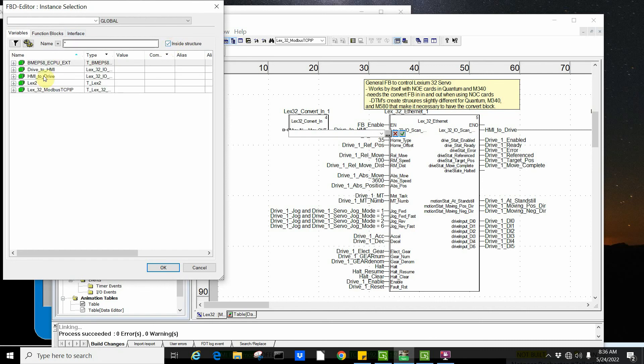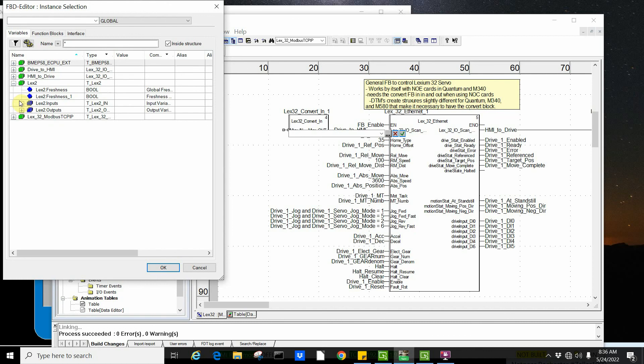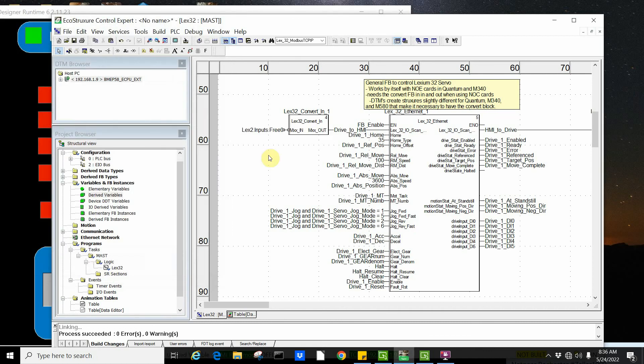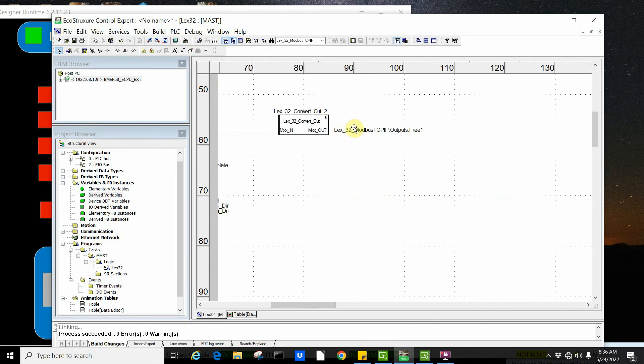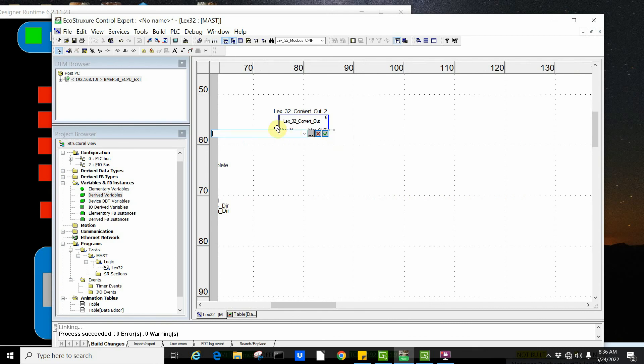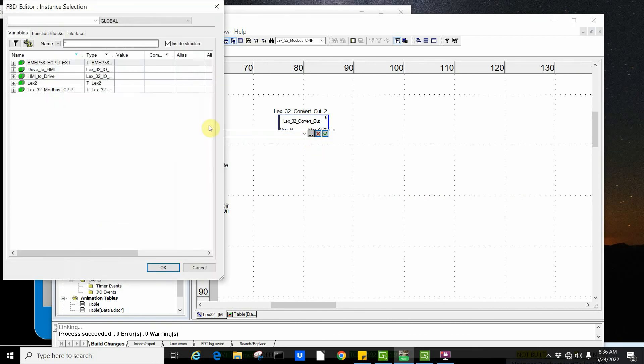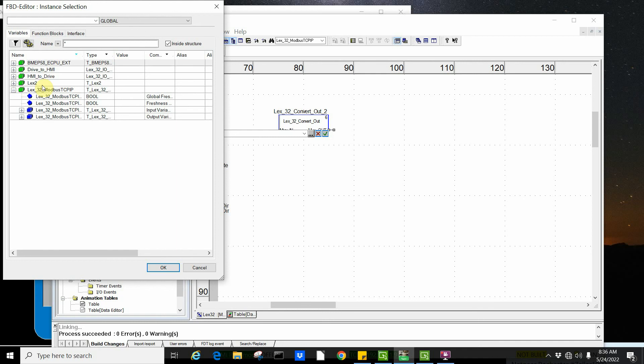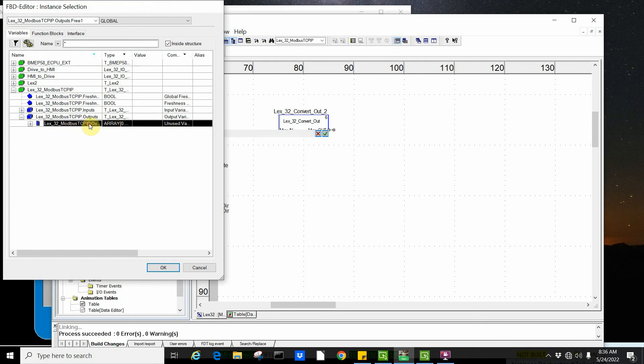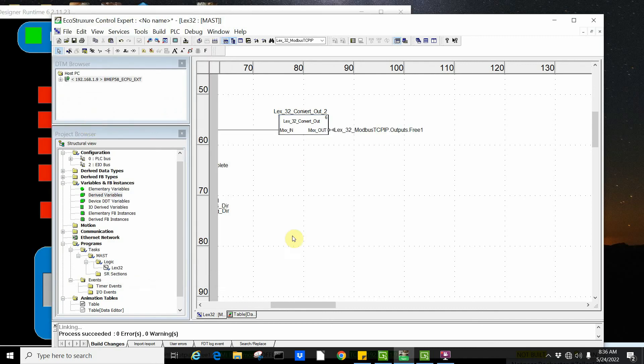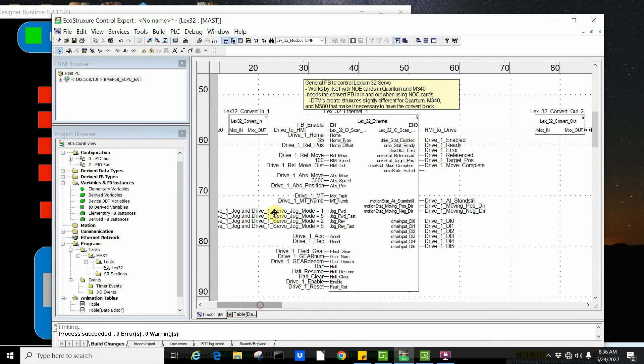I align it with the drive I just created for the second axis. Inside the structure, here's my Lex32. I want to line that up with my inputs or status coming back, the array of 27. I do the same thing on the output. Go to where I have the array of 27 here. Then if I just change these to variables that make sense that go with the second axis, you would now be controlling the second axis.